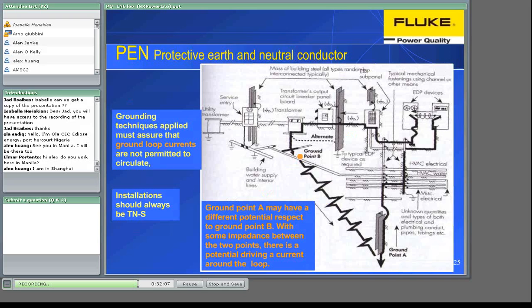Protective earth. A neutral-to-ground measurement is expected to be 0 volts or close to it. If the measured voltage is much higher, it indicates the presence of a ground loop caused by grounding at two or more locations. Good grounding is an important issue in order to avoid ground loop currents. All sensitive electronic equipment must be properly grounded to assure both safety and proper operation. Large computer installations such as those of data processing or process control need special attention because they consist of many separate pieces of equipment that are interconnected.